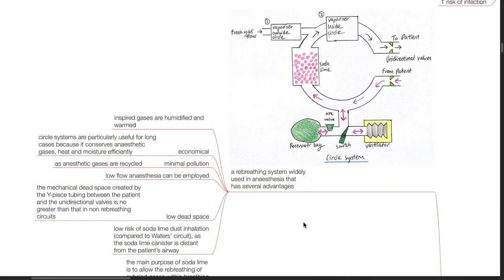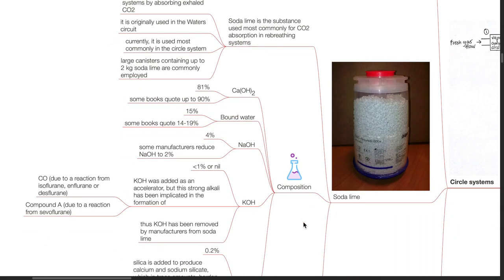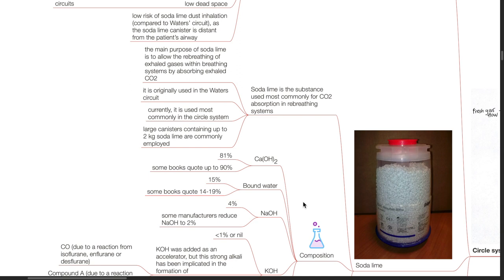There is a low risk of soda lime dust inhalation compared to the Waters' circuit, as the soda lime canister is distant from the patient's airway. Soda lime is the substance commonly used for CO2 absorption in re-breathing systems. The main purpose of soda lime is to allow re-breathing of exhaled gases by absorbing exhaled CO2. It was originally used in the Waters' circuit but is currently used most commonly in circle systems. Large canisters containing up to 2 kg of soda lime are commonly employed.